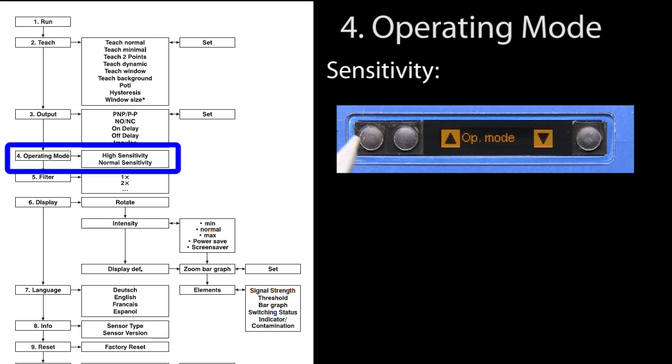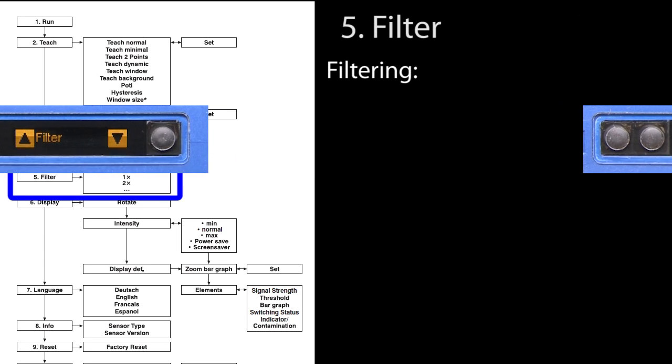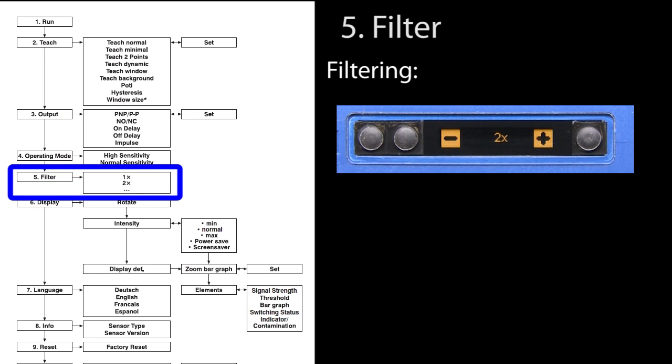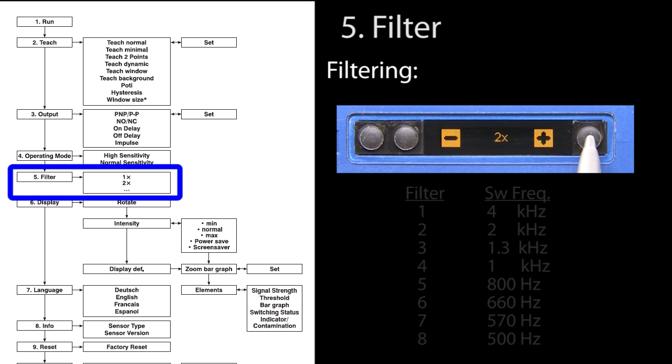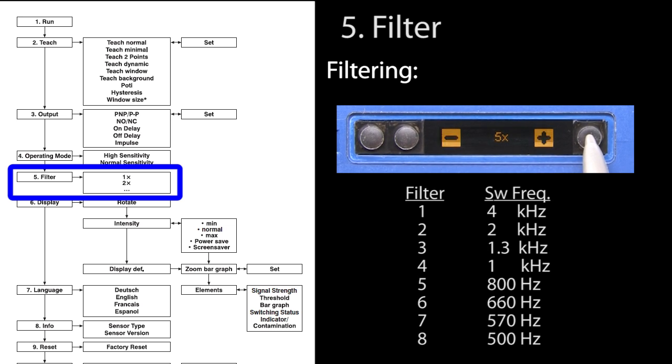Operating mode is where we set the sensor sensitivity that we mentioned earlier. The high sensitivity setting is for extending the detection range so you can detect objects a little further away. You can filter the signal to reduce false alarms. There are eight filter settings but beware, each one reduces the switching frequency of the sensor. The sensor switching frequency is how fast it can make a decision.